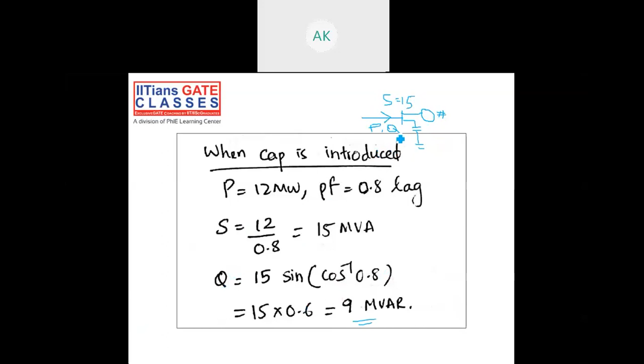So since it's 12 megawatt, the PF is 0.8 lagging. So we will calculate S, which we'll get as 15. So 15 MVA is being drawn from the main grid, right? Then if we calculate Q, we get it as 9 MVAR, which means 9 MVAR is being drawn from the grid. So this Q is 9 MVAR. In the earlier slide, we found that the motor requires 16 MVAR, right?